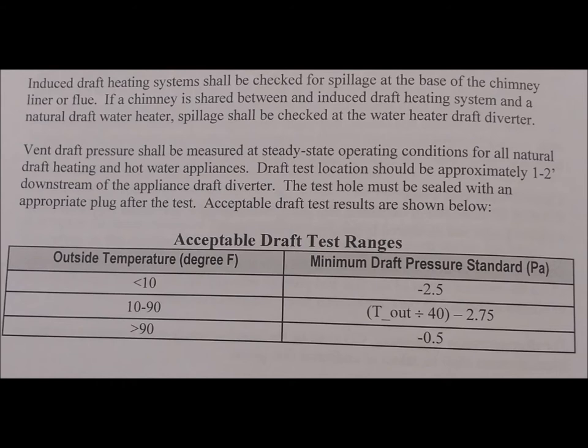Induced draft heating systems shall be checked for spillage at the base of the chimney, liner, or flue. If a chimney is shared between an induced draft heating system and a natural draft water heater, spillage shall be checked at the water heater draft diverter. Vent draft pressure shall be measured at steady state operating conditions for all natural draft heating and hot water appliances. The draft test location should be approximately 1 to 2 feet downstream of the appliance draft diverter. The test hole must be sealed with the appropriate plug after the test.